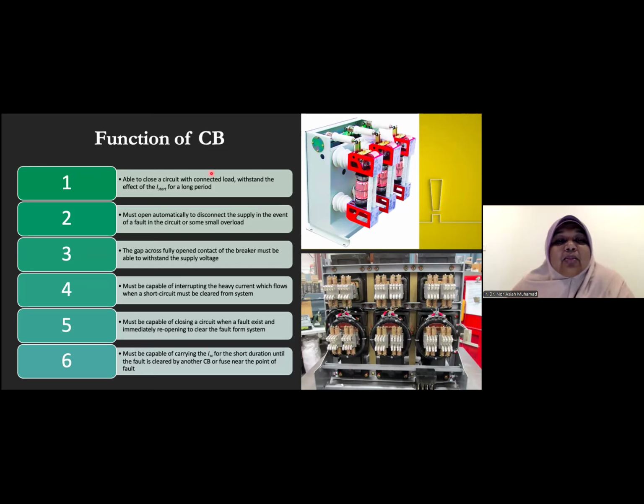So the circuit breaker function should be able to close or interrupt the circuit within the effect of the fault. So here the circuit breaker should not operate if the machine is starting, because when a machine starts it has a starting current, so the circuit breaker should not operate in this condition. So it should be able to define whether this is a starting current or a fault current. Then the circuit breaker must open automatically. So it must automatically disconnect. But to reclose, it can be automatic or it can be manual.